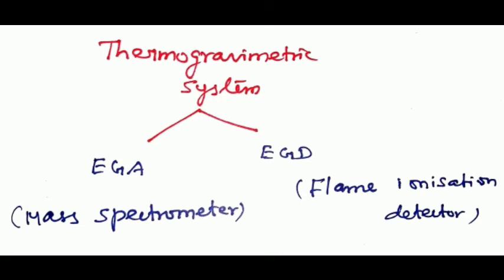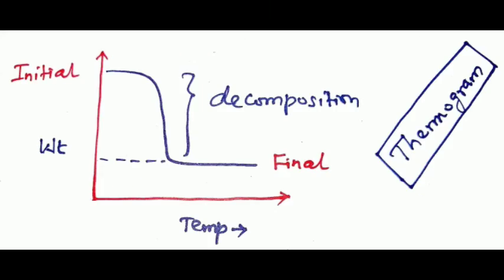In thermogravimetric analysis, the sample, usually a few milligrams in weight, is heated at a constant rate in the range of 1 to 20 degrees Celsius per minute. A thermogram shows weight change versus temperature or time. Temperature, initial and final, depends on variables such as heating rate, nature of the solid, and the atmosphere of the sample.